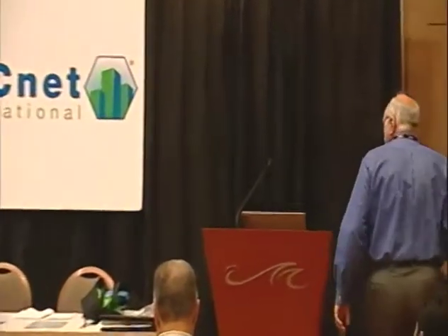Now, with respect to the objects, at this point, every boiler supplier has a different suite of objects. So we try to be flexible and say, our list is probably 100 different things, okay? If we're approving a boiler submittal and the boiler supplier comes and says, I got 1 object, well, we're not going to approve that. But he may have 80, he may have 120. So we are flexible in that way so long as it's meeting the consultant's design intent. So these boiler objects include things like fault codes, supply water set point, gas volume, runtime hours, and so on. And we're doing this because there's no way we could instrument a boiler or chiller to get that kind of information to meet, for example, the measurement and verification requirements for LEED. Okay, it would be very expensive and difficult to do that without having a BACnet interface that included metering.